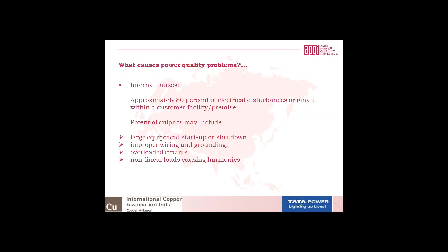While there are certain internal causes, there are also external causes. About 20% of power quality problems originate within the utility's transmission and distribution system. The most common causes are lightning and switching surges, tripping, and equipment failure in the grid. Now this tripping and failure can occur due to a variety of factors, controllable and non-controllable both: bird faults, a bird dropping a wire, a tree branch coming into the arcing zone of an overhead transmission line, animals and reptiles creeping into indoor switchgears and switchgear compartments, human interventions, or simply aging of old equipment, and ingress of moisture and dust in the equipment. Also, with normal switching operations in the grid, when you charge a very large transformer, you experience a power quality issue. There is a sudden dip in voltage.